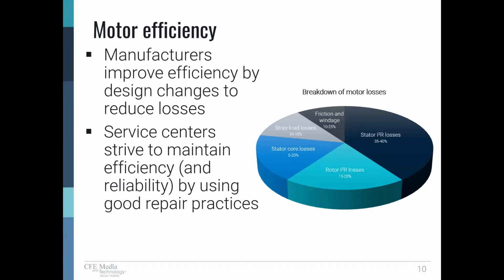And to go, let's call it further upstream, starting out with the motor itself. Motor manufacturers work to improve efficiency of the motors they build by design changes that reduce the losses in the motor. And the service center's goal, their objective, is to maintain the efficiency as built, and also, when possible, increase the reliability of that motor by using good repair practices. And we see this little pie chart with the breakdown of the motor losses. These are the things that we want to keep that pie, whatever size that pie is. We don't want it to get bigger in any one area. We don't want any of those parts of it to start bulging out.